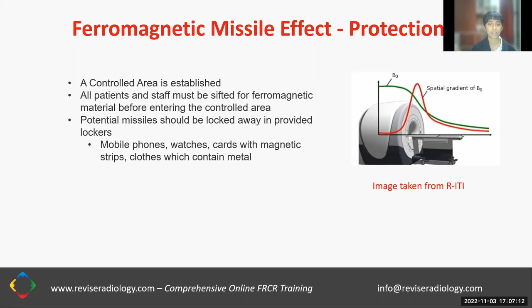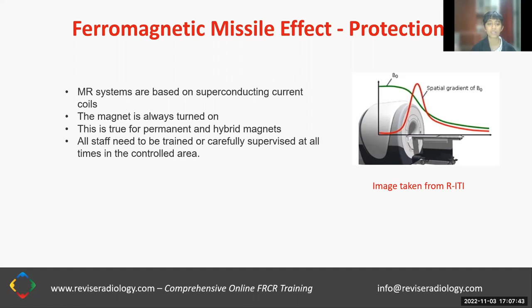Something that's really important to know is that the static field is based on superconducting current coils, and this magnet is always turned on. Even when the machine is not in use, the magnet is always turned on. This is true for both permanent and hybrid magnets. So all staff need to either be trained on how to behave in the controlled area, or if they haven't received the right training, they need to be carefully supervised at all times in the controlled area.